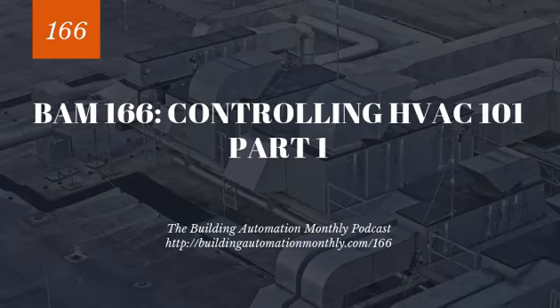Well, as I mentioned, we have these things called VAV boxes, and we have exhaust fans and exhaust ducts, etc. So in a modern office space, most of the buildings have variable air volume air handlers, meaning you keep a consistent temperature and then you vary the air volume. You've got these boxes, and these boxes have a round damper on them, and they're called VAV boxes, or variable air volume boxes. They will tend to serve either a single space or multiple spaces. It just depends on the layout.